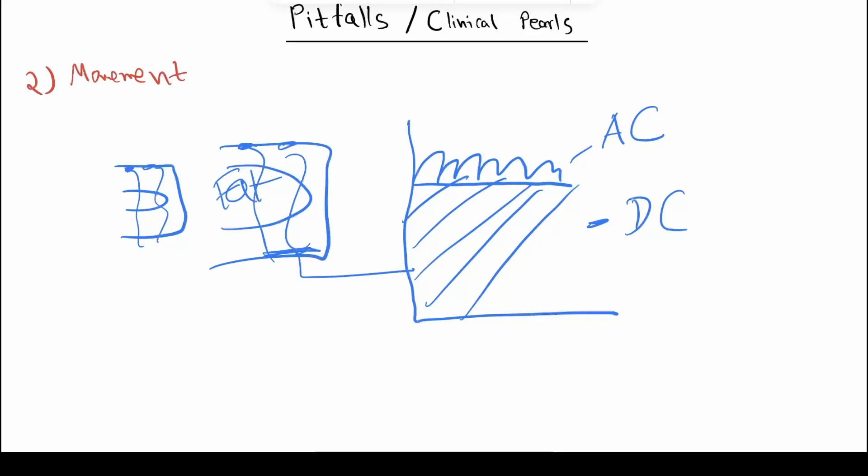The problem with this is the AC is only 2% of the entire reading. So if you move or if the patient moves or if the probe isn't placed perfectly or it's not the right size, it increases the chances of error because it's such a small percentage of the whole thing.